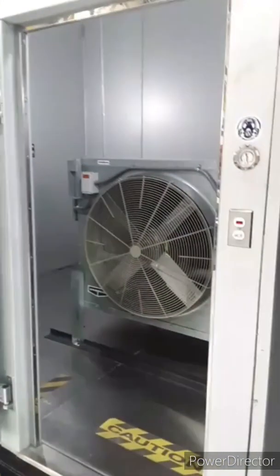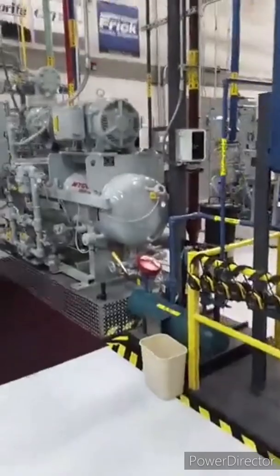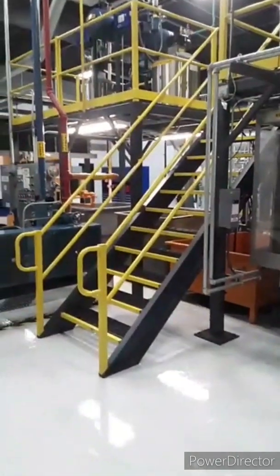Let me flip the camera around. That's our blast freezer in there — there's a fixed sensor. It is highly recommended to have fixed sensors in all areas of confined space that aren't normally occupied. Those are the intake louvers to this engine room, and as that intake louver is open, all the air will be channeled and comes this direction, making its way through the openings and up and over the compressor. It would then head back the other direction — on the other side of that surge drum is one of the two exhaust fan locations. We have our limits set at 25 ppm and 50 ppm, which determines when we have an alarm and ventilation at full potential, manual reset, etc.